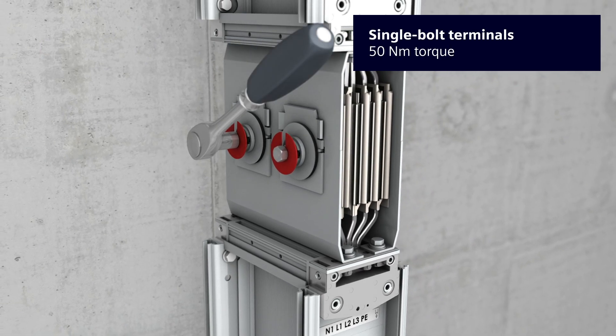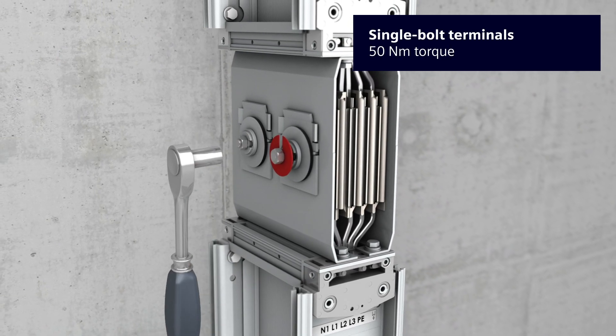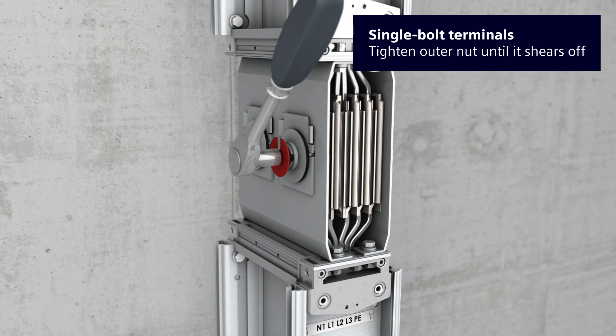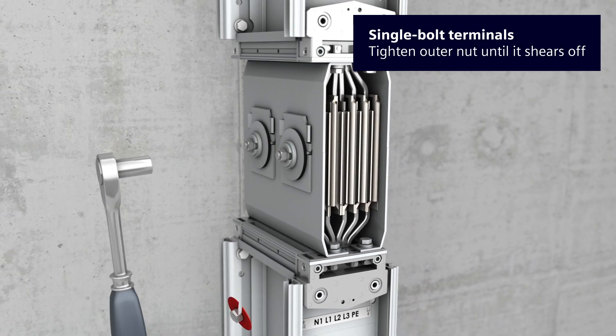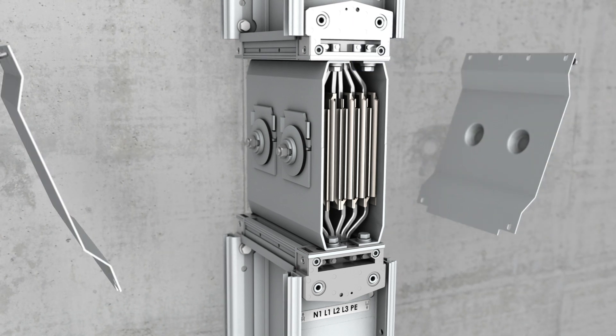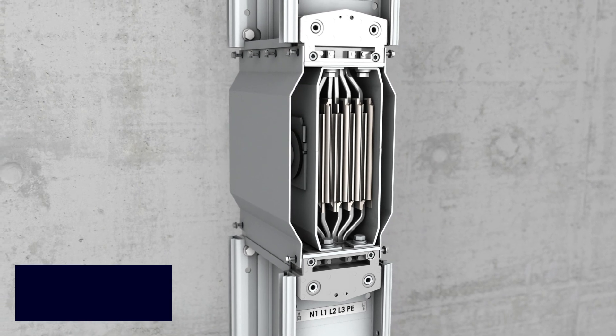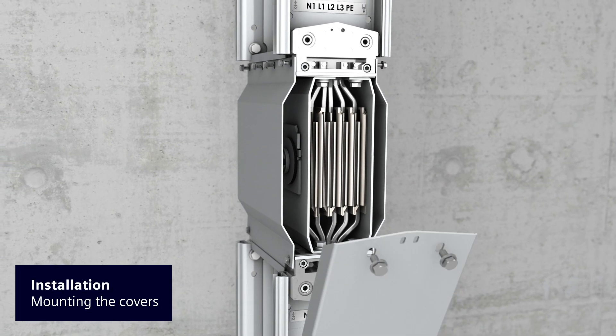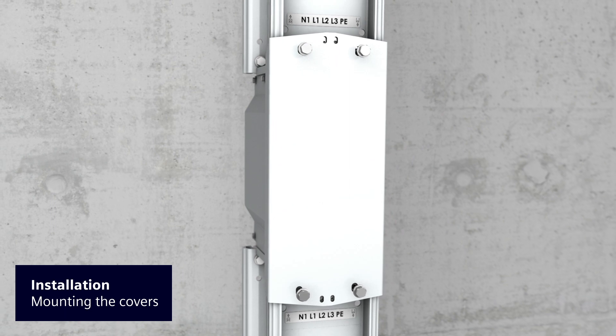During initial installation, the two single bolt terminals can also be tightened without a torque key. Tighten the outer part of the double-headed nut until shearing off. That will represent a torque of 50 Nm. Mounting the covers will complete the installation of the maintenance-free bus bar connection.